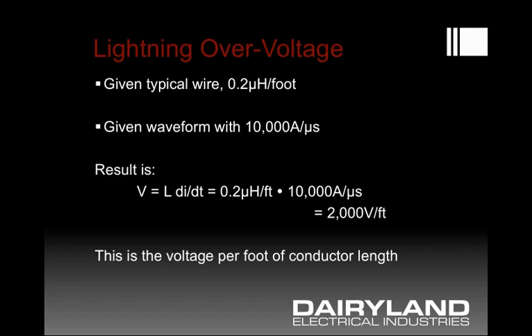Consider how many feet of conductor length might be used in some of your applications — you could exceed the insulation strength of a coating, an insulator, or other insulation system and create an arc even with a protection system installed. The reason is because the inductance is so high for the conductor length that you've installed.